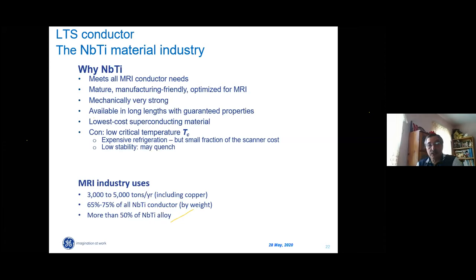We prefer to use niobium titanium so far. Why niobium titanium? It meets all MRI conductor needs. Mature, manufacturing friendly, optimized for MRI, mechanically very strong, available in long lengths with guaranteed properties. Variability of properties is within a few percent along the billet. It's the lowest cost superconducting material. The typical cost of niobium titanium wire is on the order of $1 per kiloamp meter.